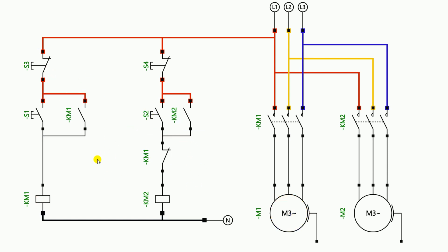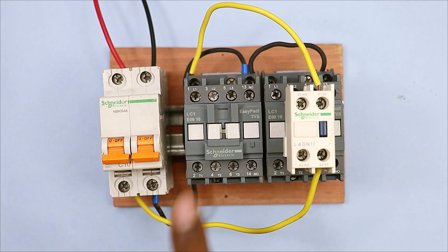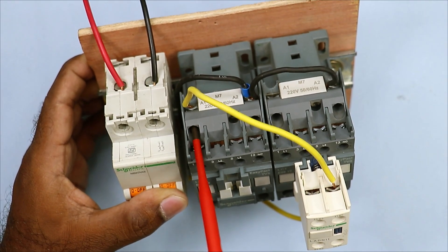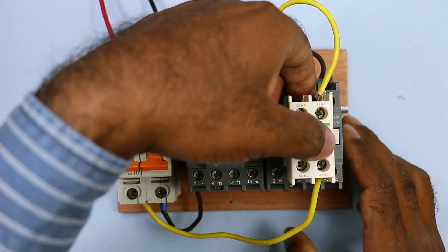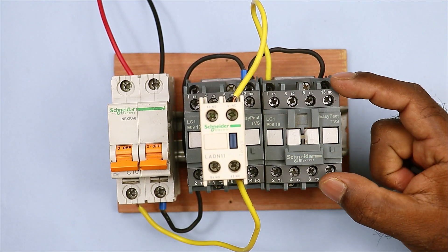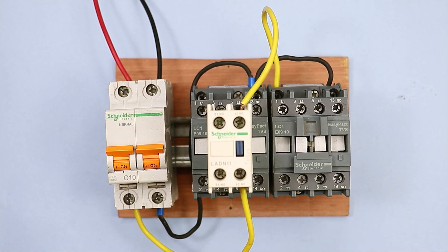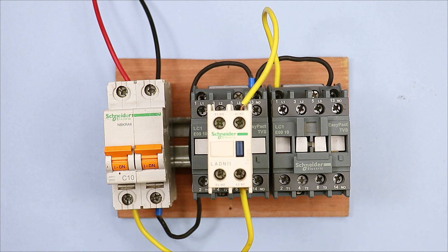Now let's see the interlocking practically. In this wiring we made a connection to start the first contactor. I am removing the phase supply from here and connecting this wire to the A1 terminal of this contactor. After that, I remove the auxiliary block from here and connect it to the first contactor. We have used the NC contact of the first contactor, and the power supply goes through this NC contact to start the second contactor. Now if I start the MCB the second contactor is on. If I then start the first contactor, the second contactor turns off.